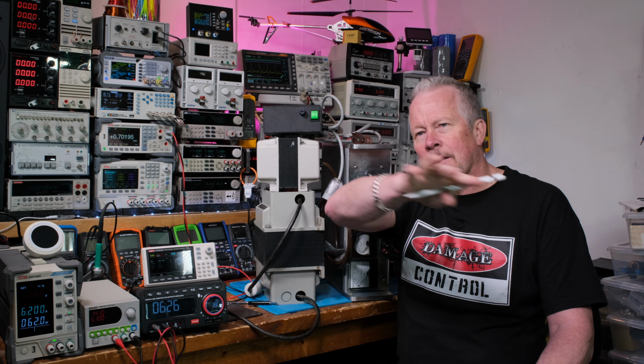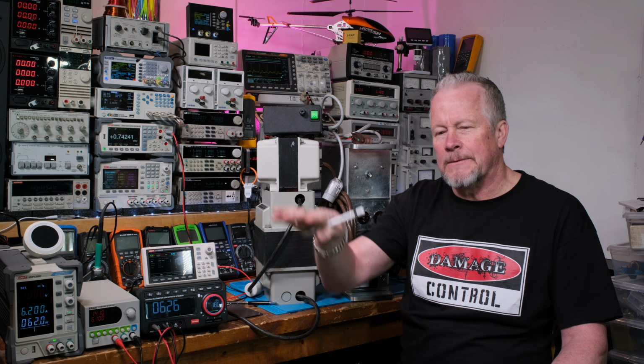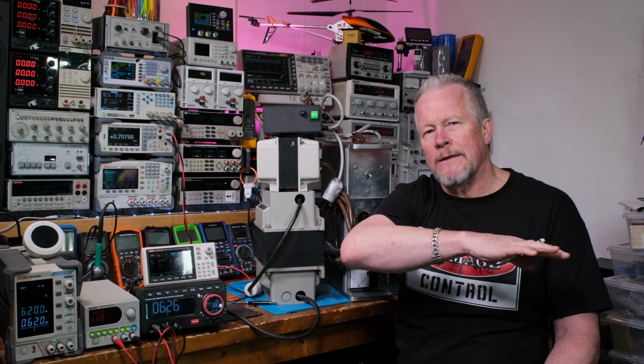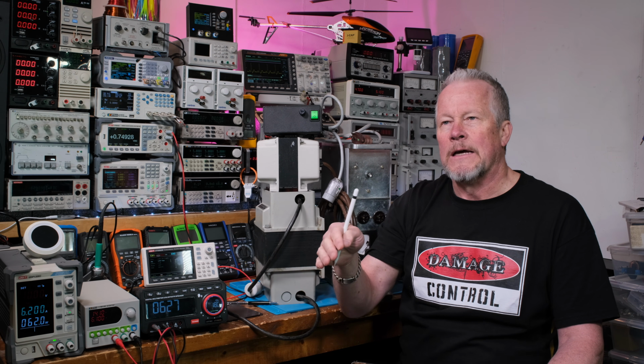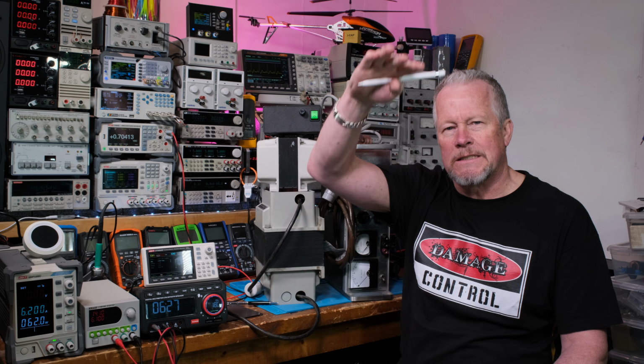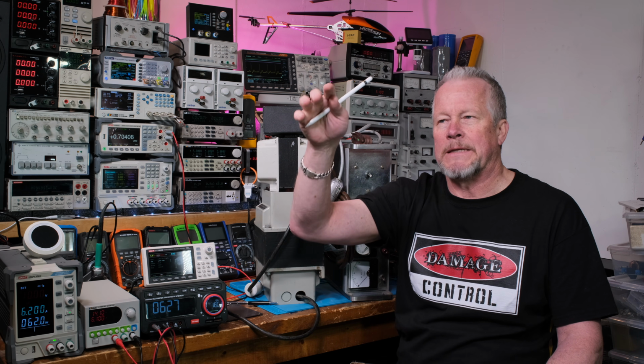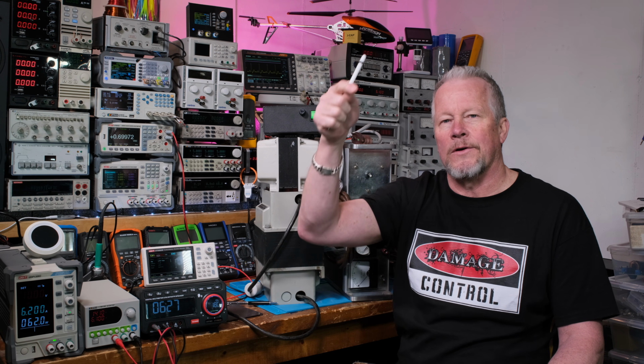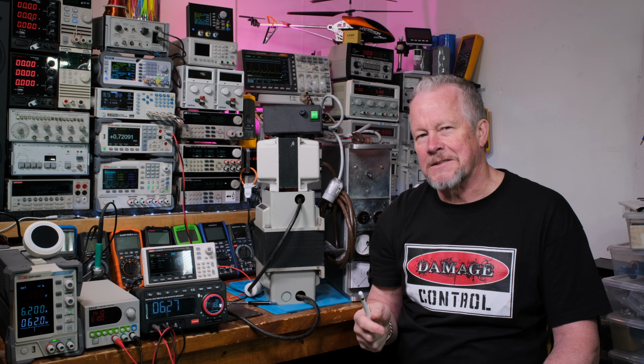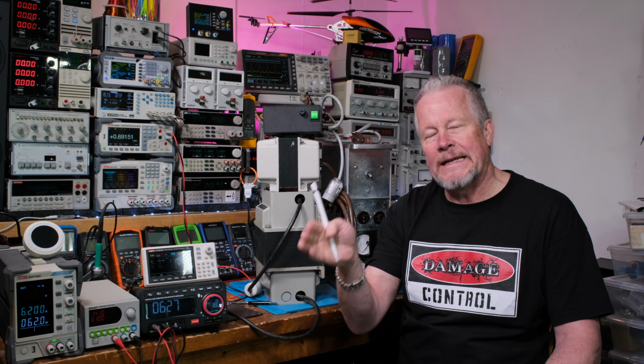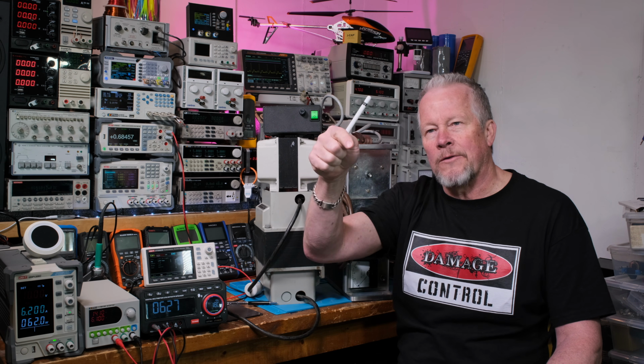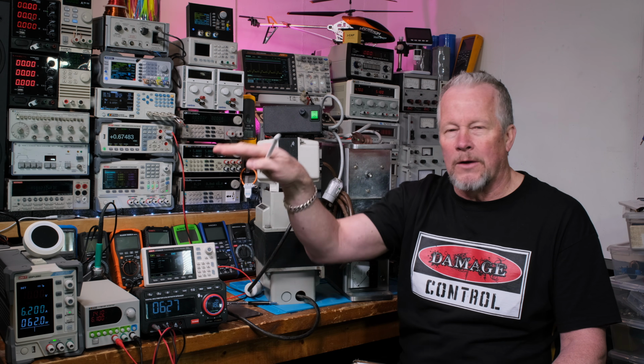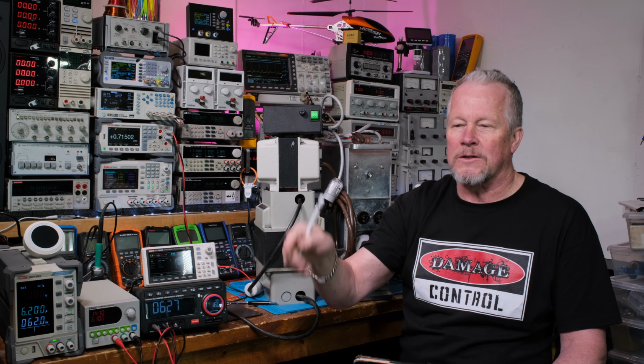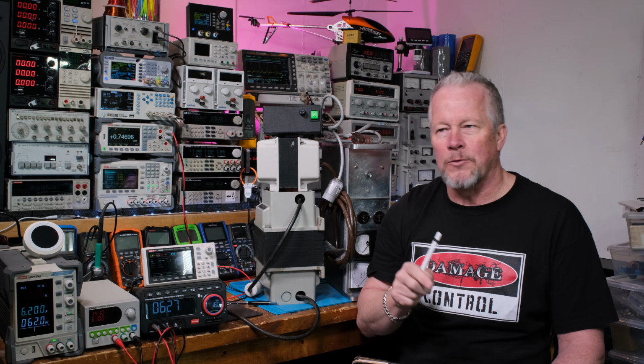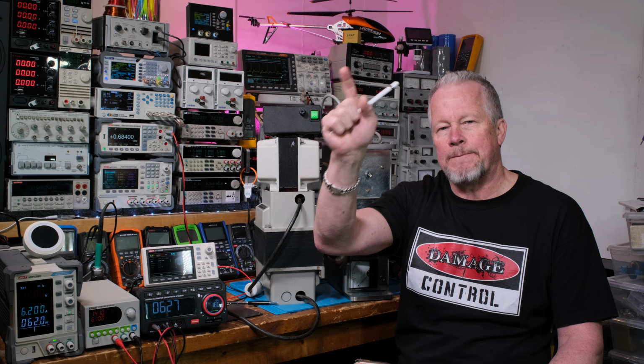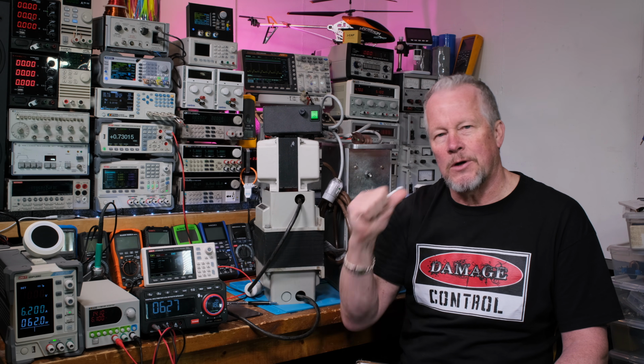That's what all those ground rods in the power system do, they give it a nice reference point and leak everything off so the floating power system doesn't float to some gigantic potential and then, like lightning, suddenly want to hit the earth and neutralize itself. But if lightning does hit the power grid system, the ground rods say, come over this way, don't go through all those wires and melt them and cause fires. Come down this way, protecting those transformers that step the high voltage down to a lower voltage that comes to our house.